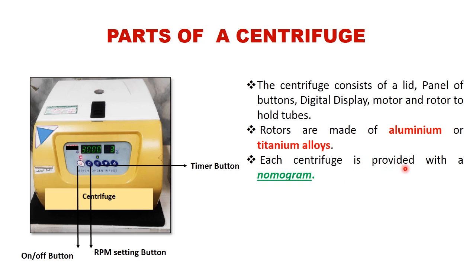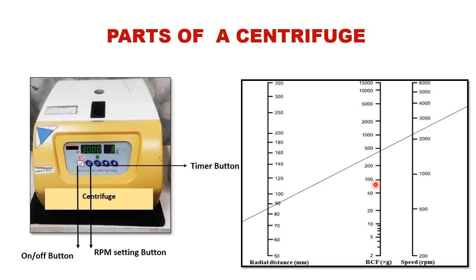Each centrifuge is provided with a nomogram. Whenever you check the box with which the centrifuge has arrived in your lab, you will see that it is provided with a catalog that is known as a nomogram. The nomogram somewhat looks like this. So here in one panel you will have the RCF, that is the relative centrifugal force, and there is the speed which is expressed in RPM. So it is used for interconversion between RPM and RCF.